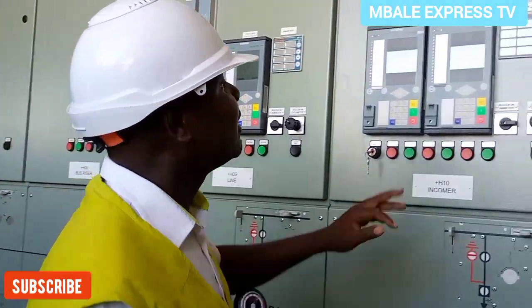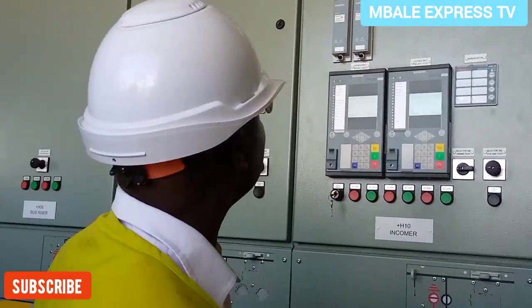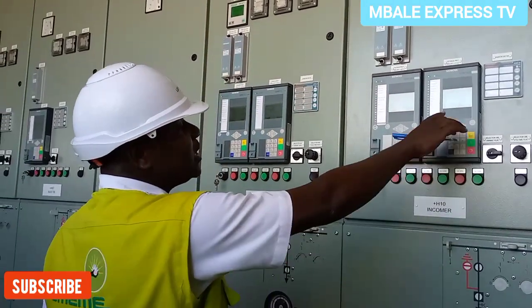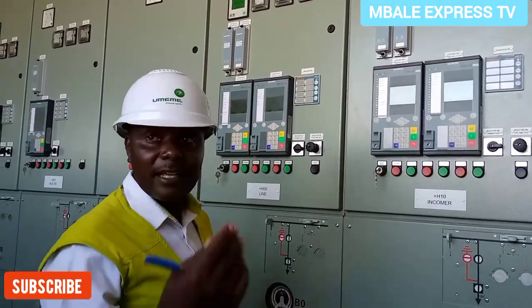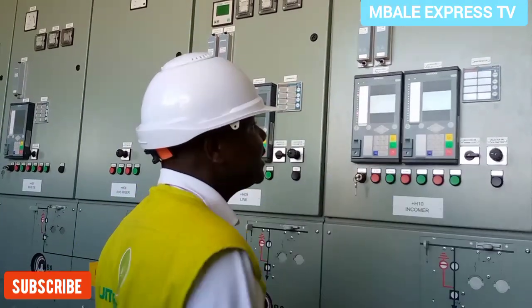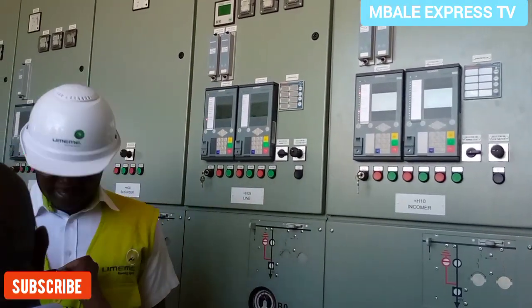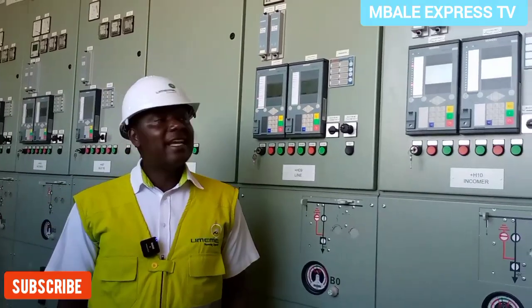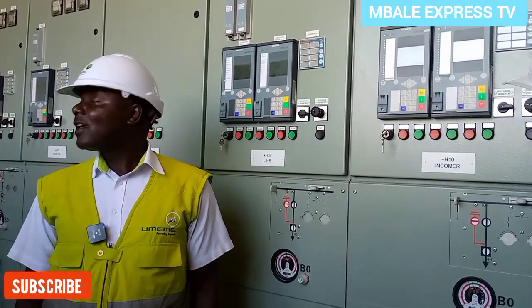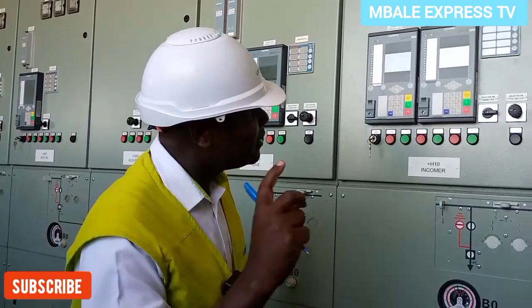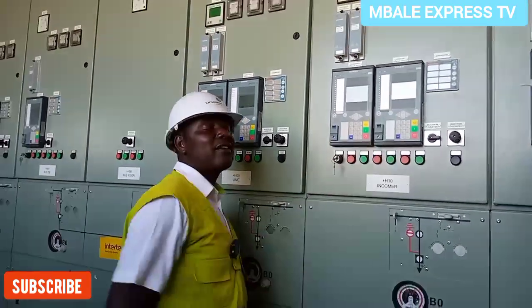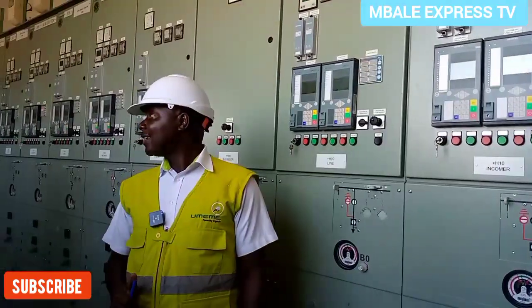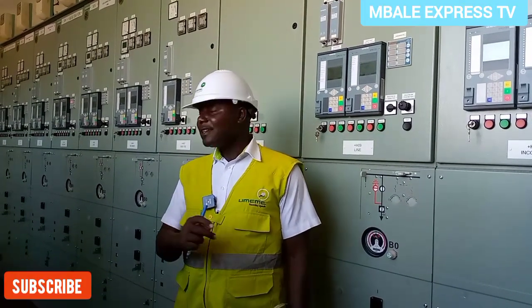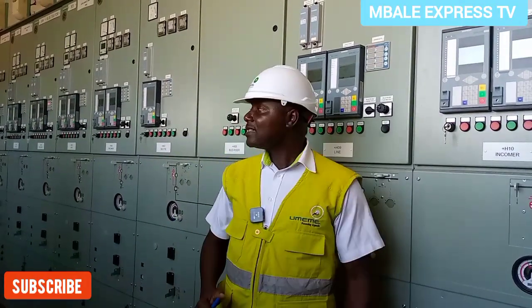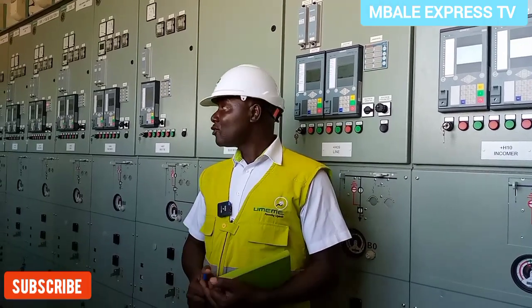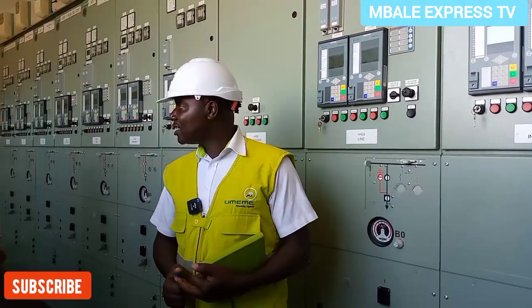As of now, we are seeing that what they are generating, they are giving us on the bus is 293 amps on high voltage in the 33 kV. If you convert it to MVA, we are getting 16 MVA right now as we are talking. But their capacity, depending on the water levels, is supposed to give us, as per design, 22 megawatts.